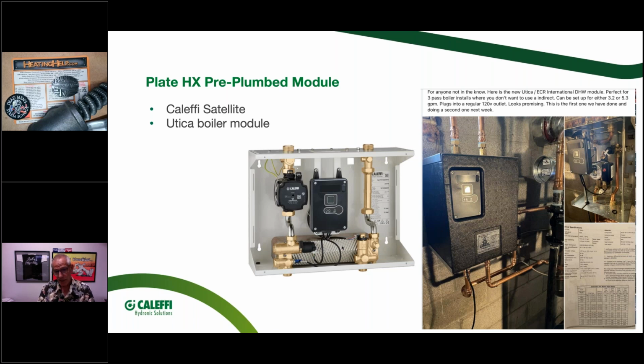Some of the flat plate heat exchangers are limited on temperature on the A side because if they're put together with rubber gaskets, like the bolt-together type, the limitation is those rubber gaskets, or EPDM, whatever they might be. A brazed type can go a little hotter, and if you're going to super high temperatures, like maybe a power plant regeneration application, that's where they go to shell and tube type heat exchangers, because they don't have a gasketed assembly or connection.